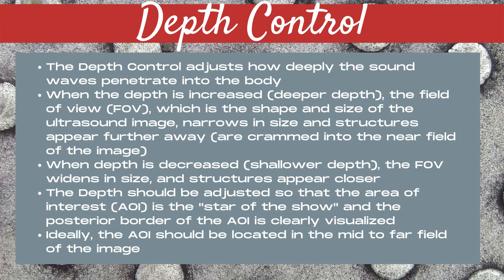When the depth level is decreased, meaning there's a shallower depth, the field of view widens in size and structures appear closer. The depth should be adjusted so that the area of interest is the star of the show and the posterior border of the area of interest is clearly visualized and not cut off on the bottom of the image.